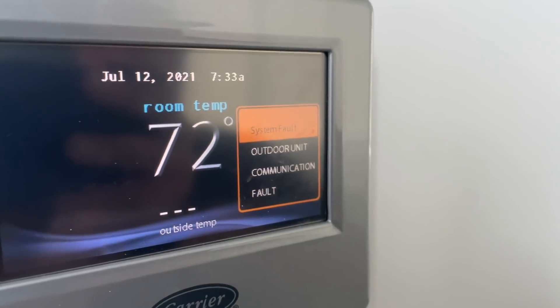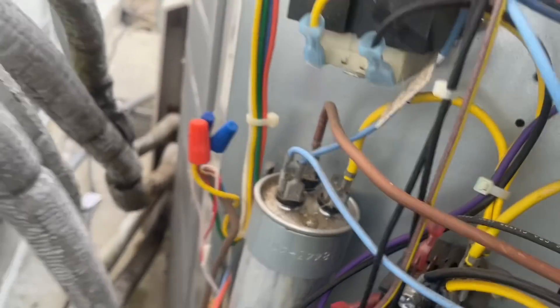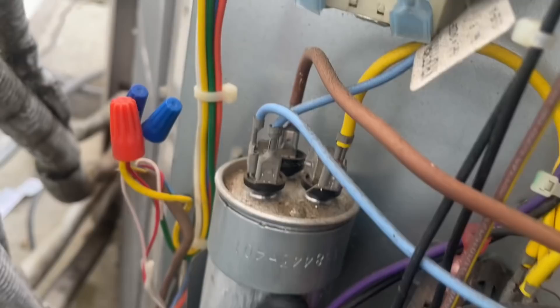The condenser — I took the power out. Let's quickly take a look at this outdoor unit. There's this control board that communicates with the system. Let's take a look at this cap — she looks a little swollen on top.